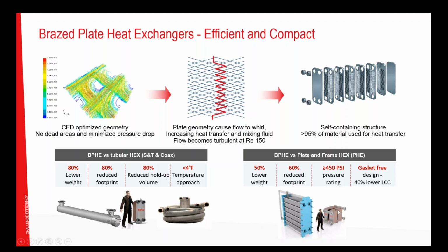It doesn't have gaskets. So if you have, like for free cooling, a heat exchanger that is not used for half the year, if you can have a small heat exchanger standing in a corner and not bothering anyone, and then for half the year it starts to save a fair amount of money, that is a better economic discussion than having half a room full of a heat exchanger that is not working for half the year.